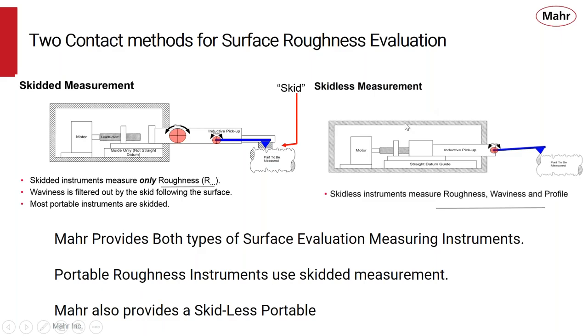A skidless measurement system operates a little bit differently, where there's a very precise datum guide in the probe, and the probe is dragged over the part, comparing any variation to that reference datum. So this allows us to see profile, waviness, and roughness all at the same time. So Mahr provides both types of evaluation systems. Most of the portable roughness instruments are skidded measurements, but we do also have a skidless portable system.